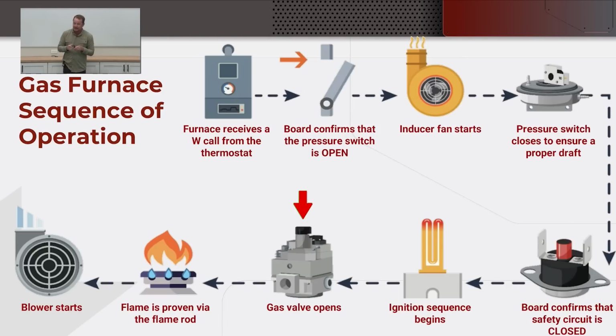And the reason for that is because the longer an igniter stays heated up, the longer that it's applying power to the igniter, the more likely that igniter is going to fail, or the reduced life of that igniter. So a lot of manufacturers will say it's a 5-second heat up time or 10-second heat up time or whatever. That isn't consistent. On a lot of the modern furnaces, the board is going to try different timings in order to keep that igniter energized for the lowest possible amount of time.